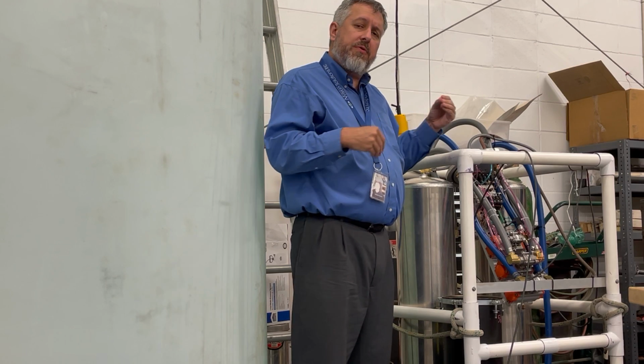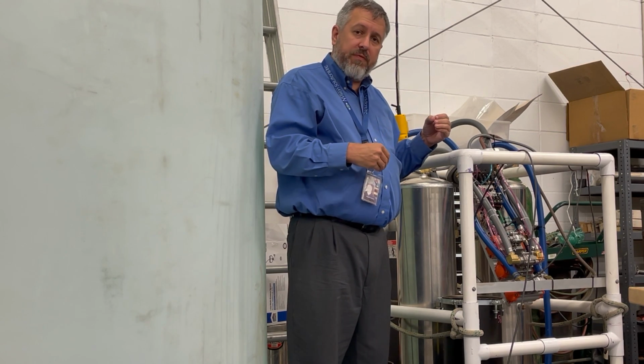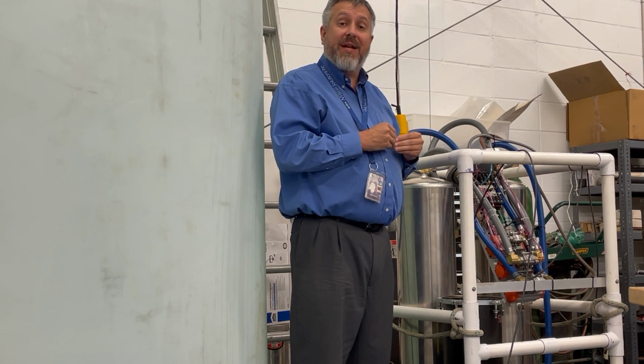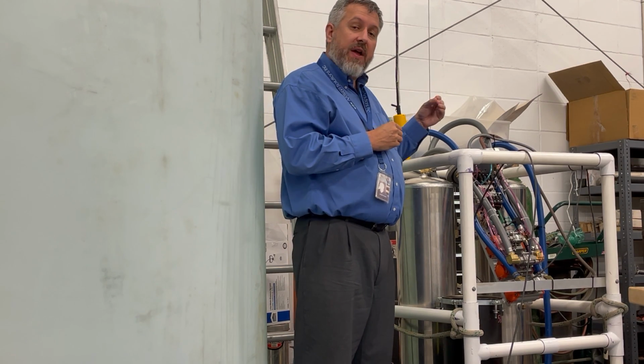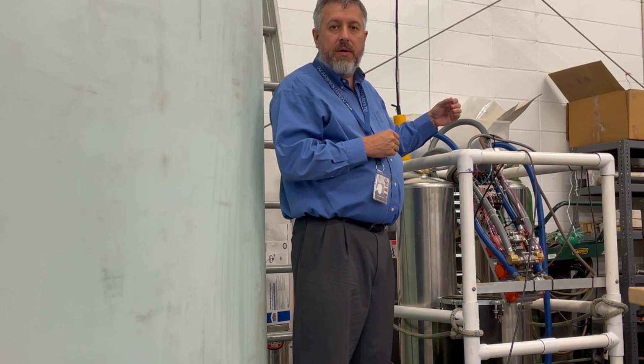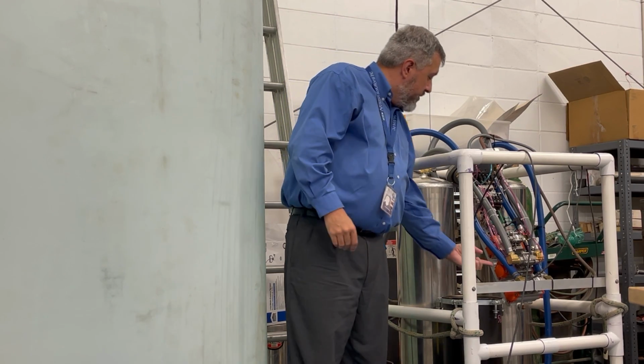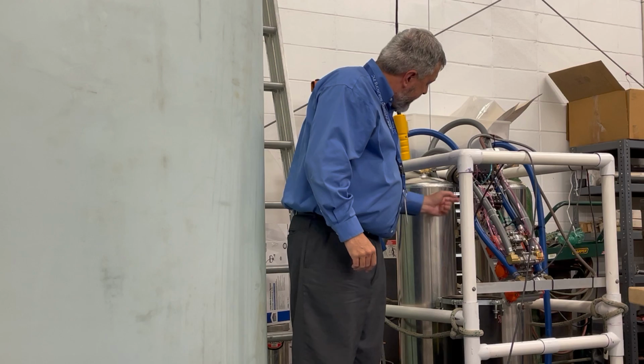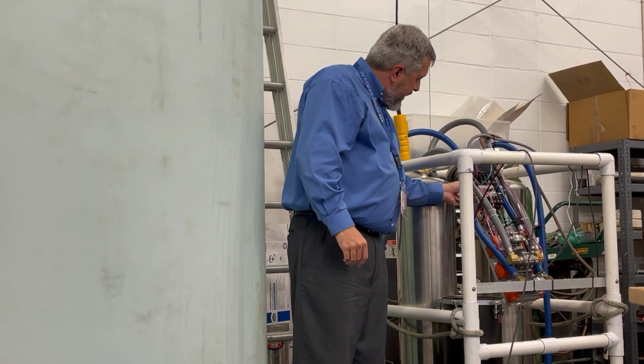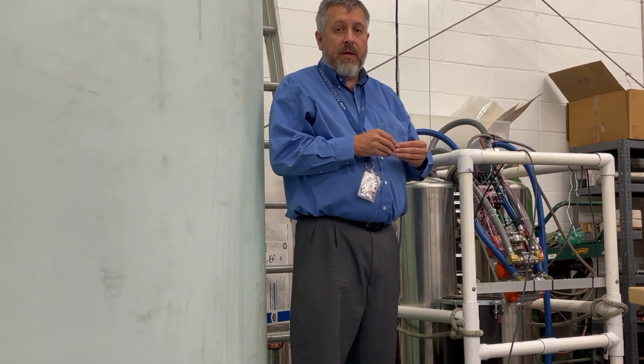For us to control the air through the system, we use air-controlled valves, which are in turn controlled by electrically controlled valves. So pneumatic valves that are controlled by electronic valves off the compressed air system.